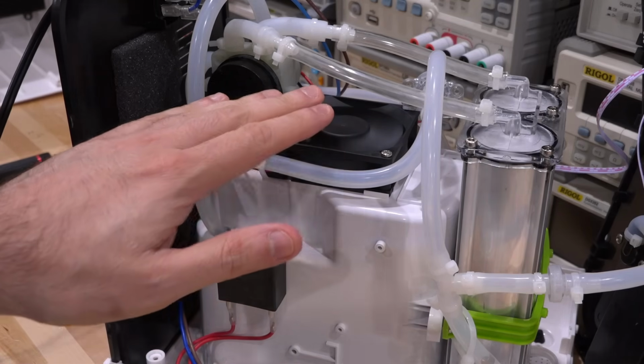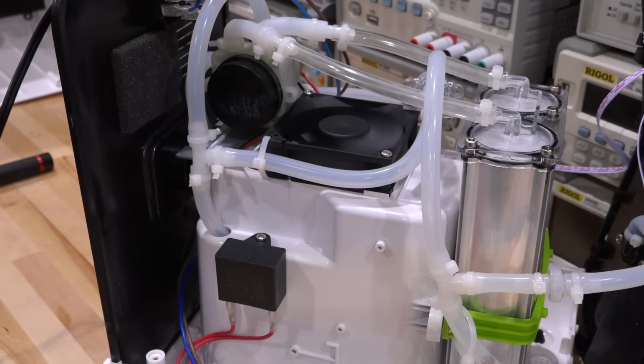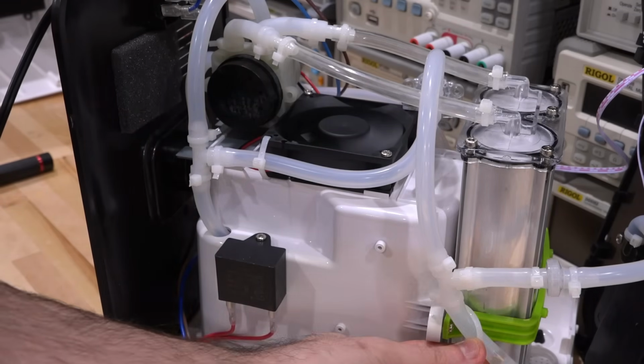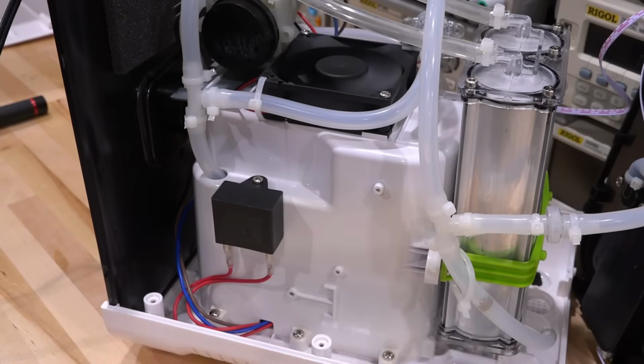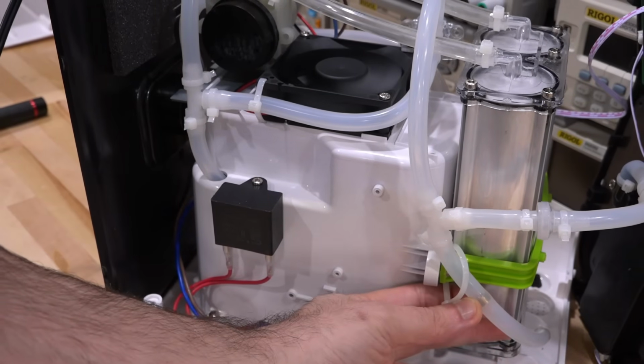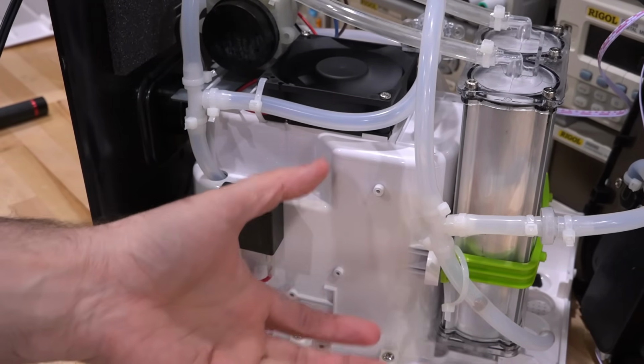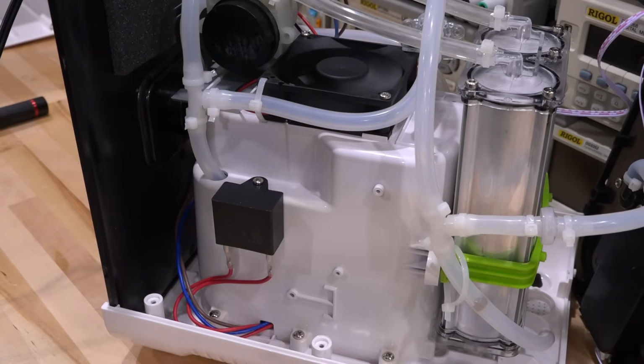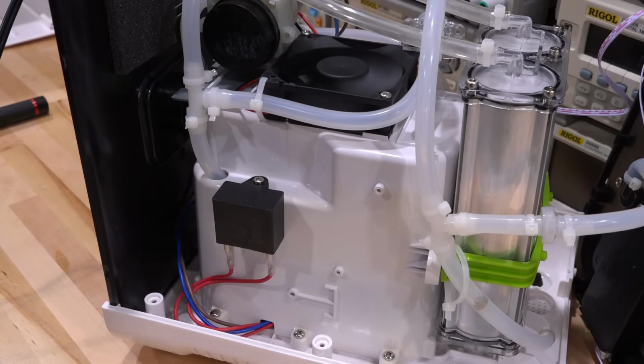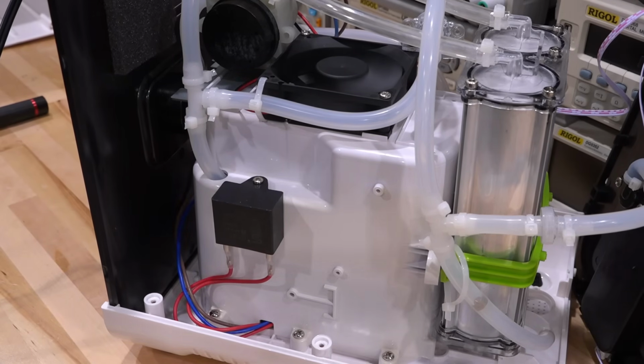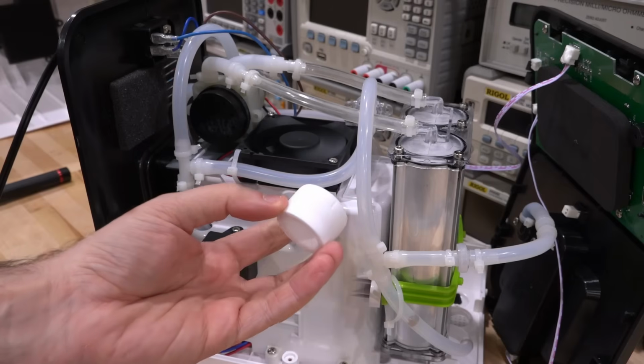The fan runs for a little bit longer after the unit's been turned off in order to cool everything down further. And here's the main oxygen line coming out. Here you can see there are some beads inside of this. I believe these are noise suppressors so that the noise of the compressor doesn't travel through the tubes and come out all the way into the user, because you're going to be close to your ears. Yeah, that's about it.